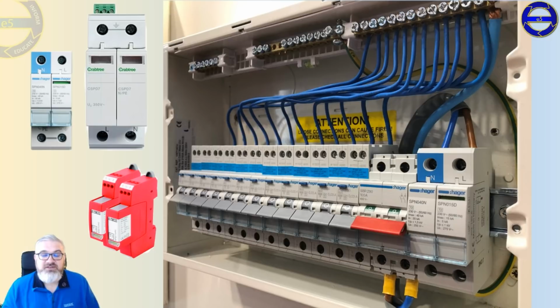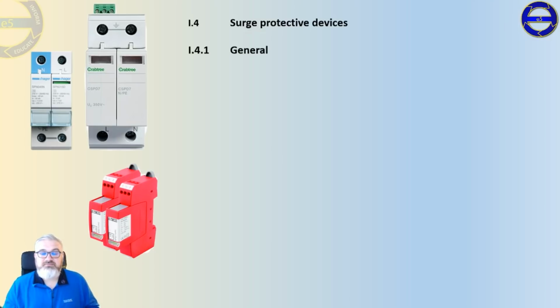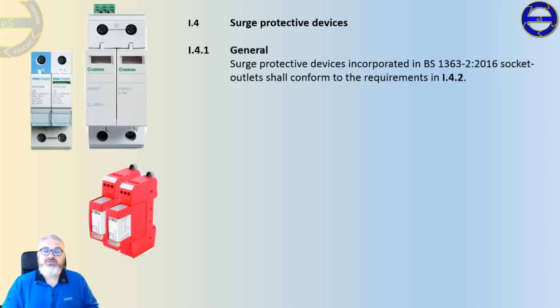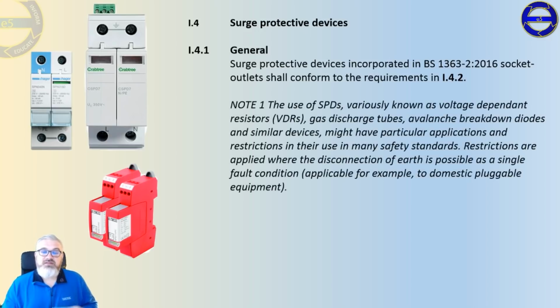So, relevant stuff. How relevant to these? Well, section I again, 4.1 general. Surge protection devices incorporated into socket outlets shall conform to the requirements in I.4.2. Again, more criteria. The note that comes with it is the worry. It states the use of SPDs, surge protection devices, variously known as voltage dependent resistors in old money, gas discharge tubes, avalanche breakdown diodes and similar devices, might have particular applications and restrictions in their use in many safety standards.